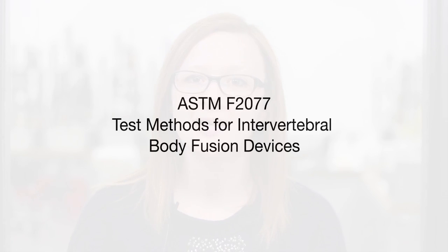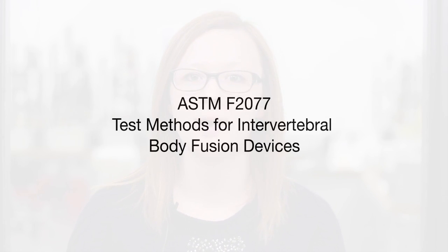Now that we have reviewed some of the general guidelines, let's discuss the three test standards in today's video. The first type of testing we'll cover, static and dynamic construct testing, is typically performed in accordance with ASTM F2077, test methods for intervertebral body fusion devices. ASTM F2077 is used to provide a standard comparison to a predicate device. The test program contains compression, compression shear, and torsion tests. Testing should consist of six of the worst case constructs for both static and dynamic testing.